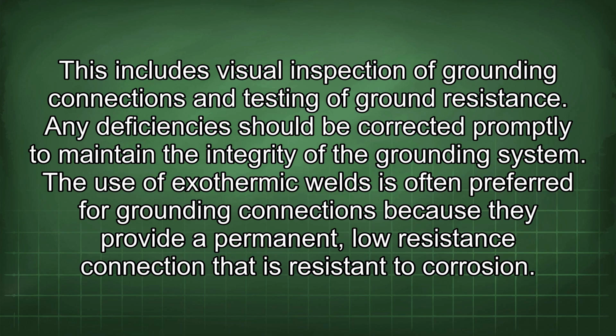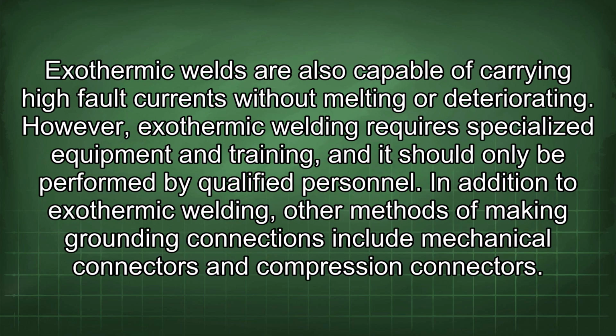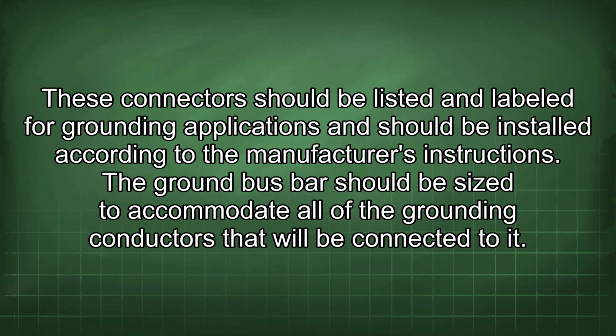The use of exothermic welds is often preferred for grounding connections because they provide a permanent, low-resistance connection that is resistant to corrosion. Exothermic welds are also capable of carrying high fault currents without melting or deteriorating. However, exothermic welding requires specialized equipment and training, and it should only be performed by qualified personnel. In addition to exothermic welding, other methods of making grounding connections include mechanical connectors and compression connectors. These connectors should be listed and labeled for grounding applications and should be installed according to the manufacturer's instructions.